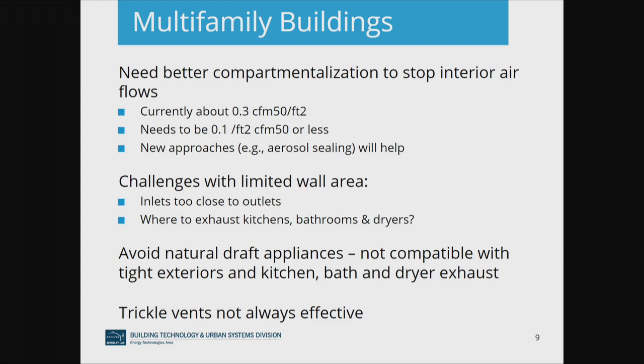There's all sorts of issues about where do you put the inlets and outlets. If you're looking at most multifamily buildings, they don't have much wall area. And we try to do things like have the inlets far away from the outlets - like if you're cooking and you turn on the range hood and vent it to outside, you don't want to be sucking your supply air in right next to it, or next to a dryer vent or anything like that. So there's a whole bunch of issues that are new in terms of we're trying to figure out what's going on, and are also new in terms of we don't actually have a great answer to that.